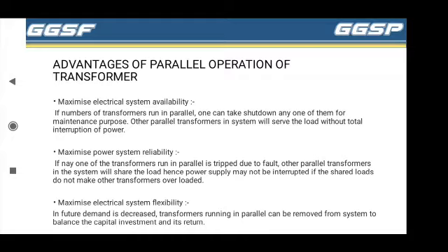Second, maximize power system reliability. If any one of the transformers running in parallel is tripped due to a fault, the other parallel transformers in the system will share the load, hence power supply may not be interrupted if the shared loads do not make the transformers overloaded. And third and last advantage, maximize electrical system flexibility. If future demand decreases, transformers running in parallel can be removed from the system to balance the capital investment and its return.